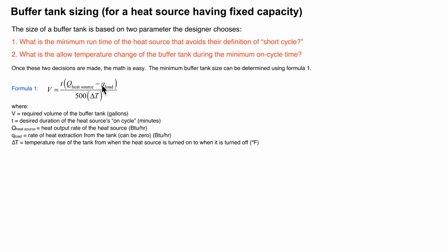And from that, we could subtract the minimum load that could be running at the same time. Now, that can be zero. You can turn a heat source on and simply charge a buffer tank up with heat without having a call for heat from the distribution system. That is one control option, okay?